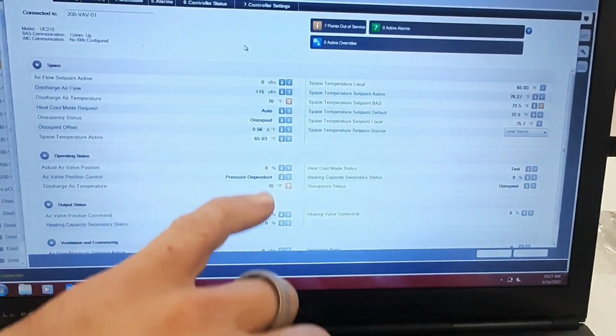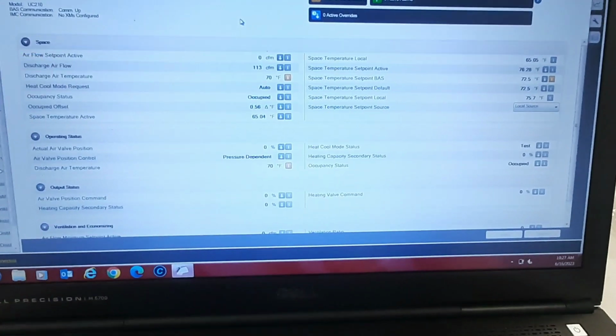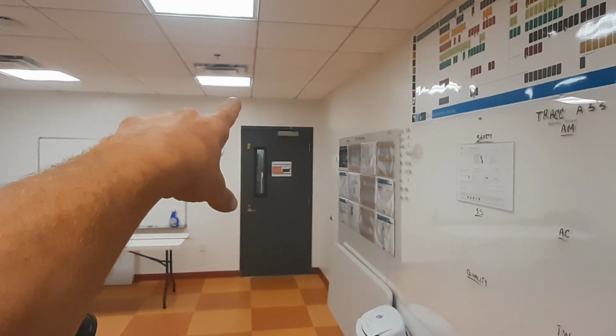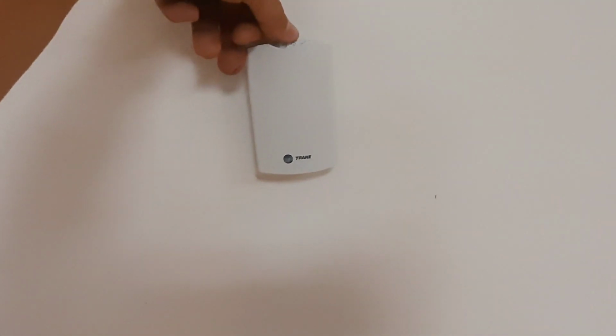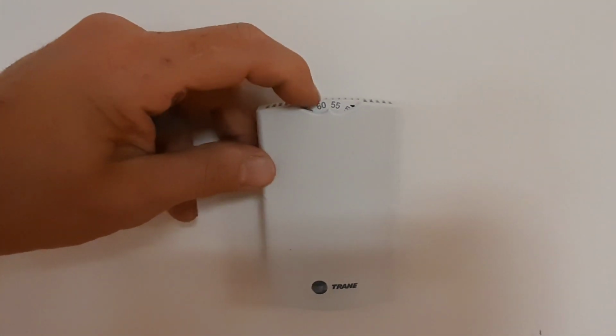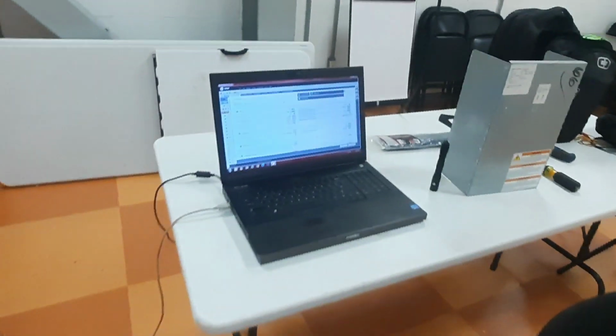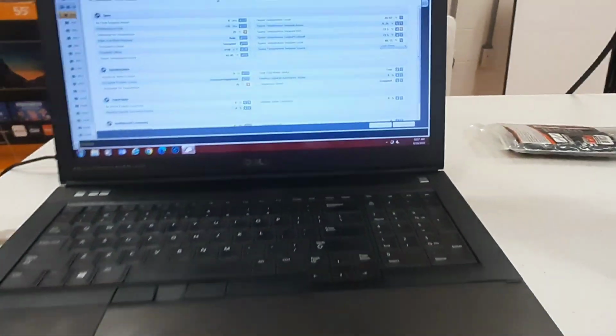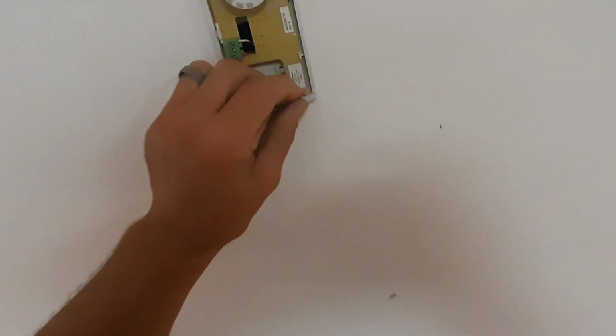So let's do something here. I'm gonna leave my CFM minimum at 0 because I don't need this one to ventilate all the time. I've got a minimum on the other VAV, so these will dump some air, and if they come in here and crank the thermostat down, I've got the low setting at 65, which I'm at 65 degrees. It cooled off quick. Just that little bit of opening cooled it down pretty quick.